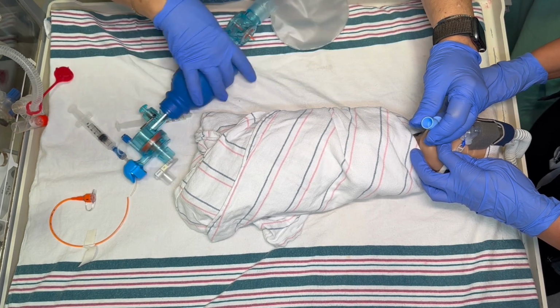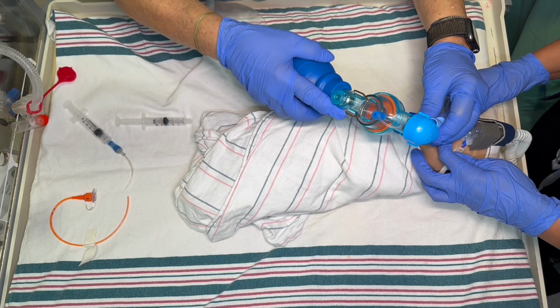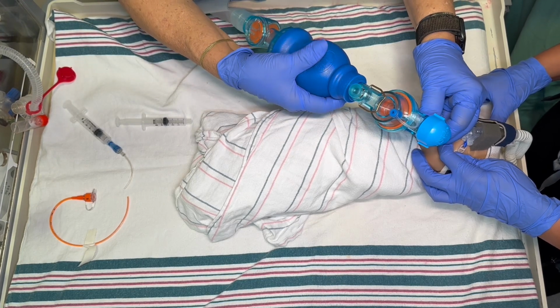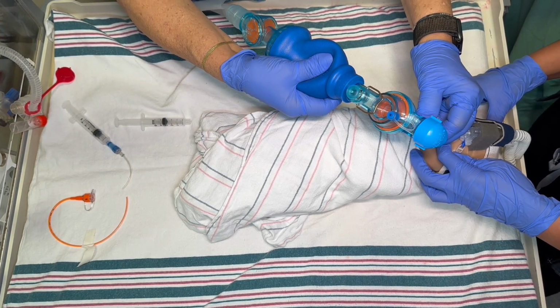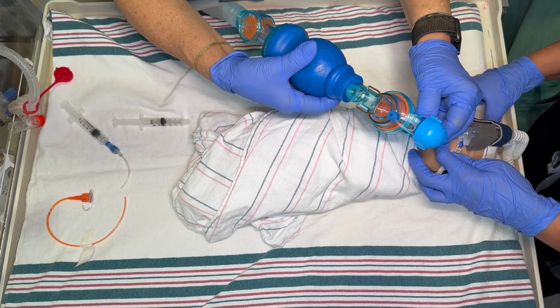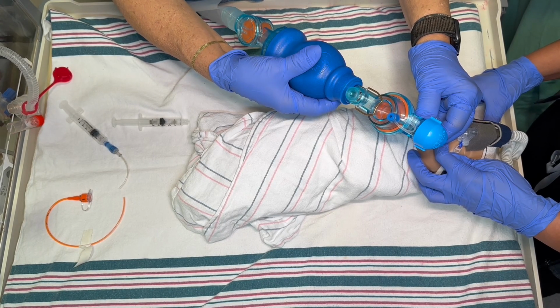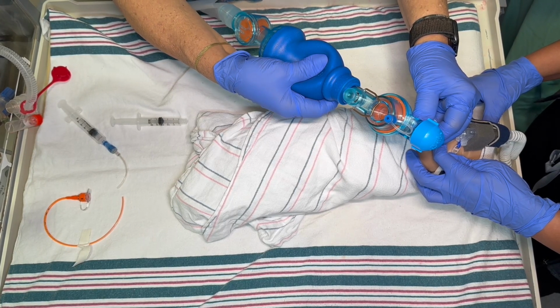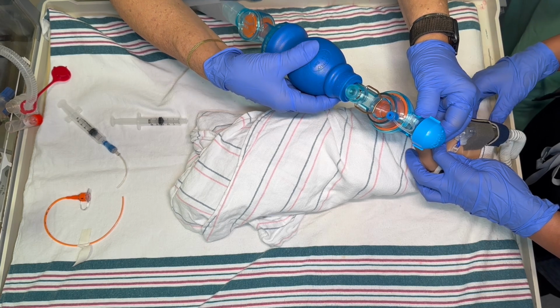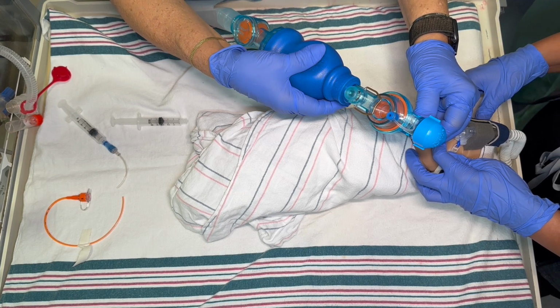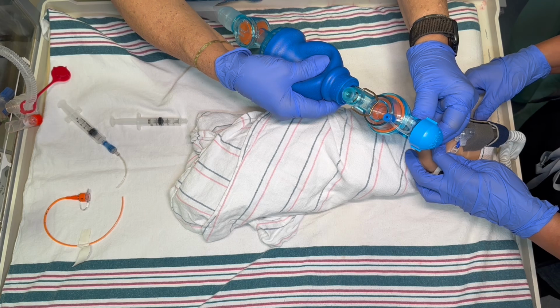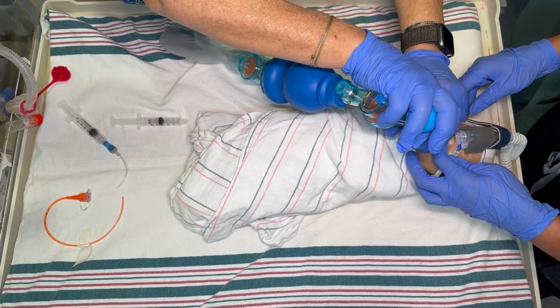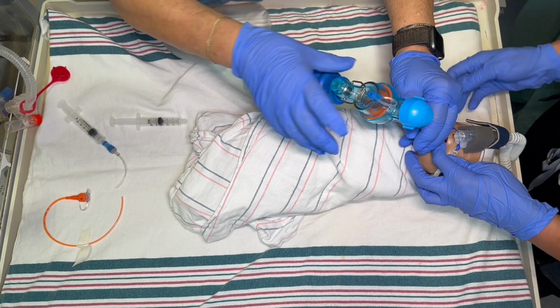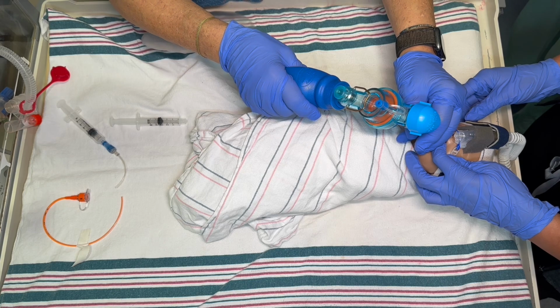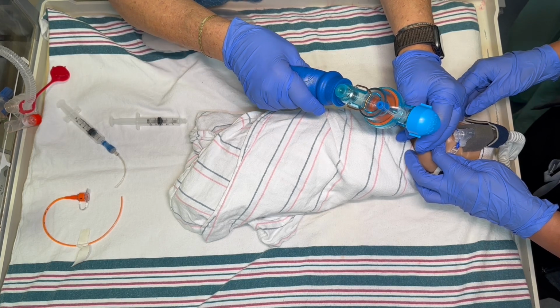Replace the ambu bag and provide another 10 breaths or 20 to 30 seconds of time. Repeat again as needed, but if this is your final aliquot, provide 15 breaths or 30 to 45 seconds of time. We allow this additional time to make sure that all the surfactant has been adsorbed before removing the device.